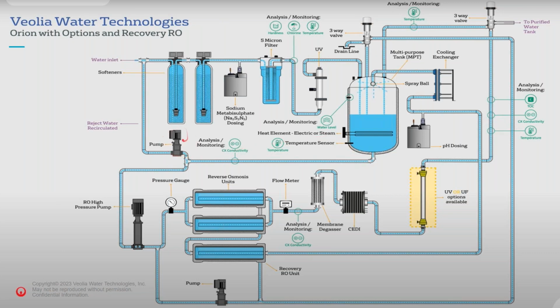Now there is an option, and you see a pump here, to also hot water sanitize the pre-treatment. That's an option where we can change the vessels here from GRP plastic vessels to stainless steel 316 Ti stainless steel vessels, and then we can also hot water sanitize and mitigate any risk with the pre-treatment here again. Same thing, raised to above 80 degrees and then cool down. So that's essentially how the system works, and essentially how we have a couple of features in terms of water saving, in terms of the recovery RO, and the reduced water to discharge during recycle using the cooling exchanger on the return line here.